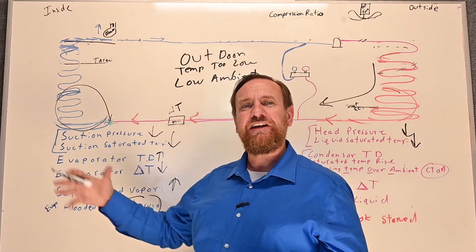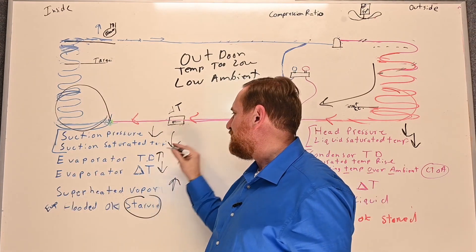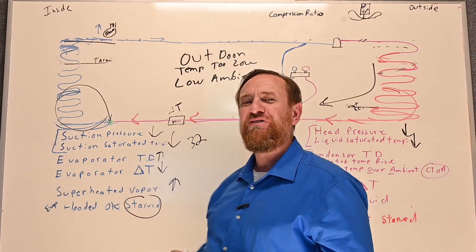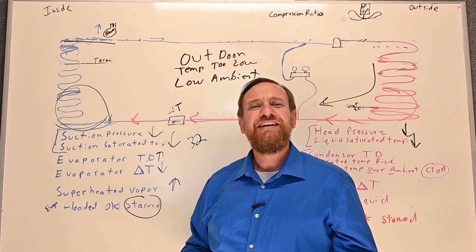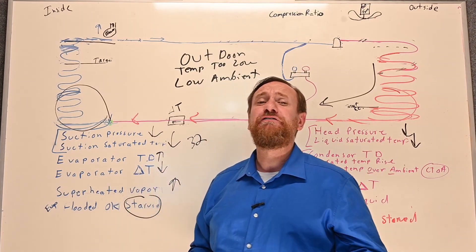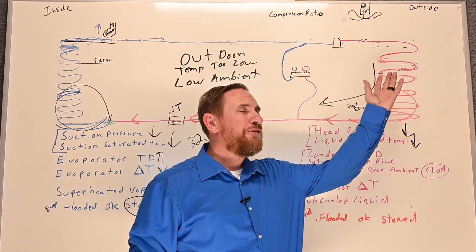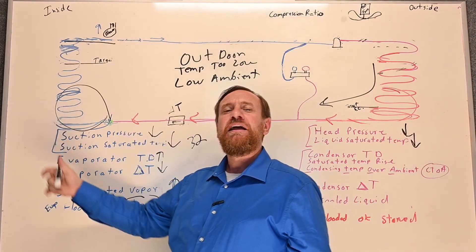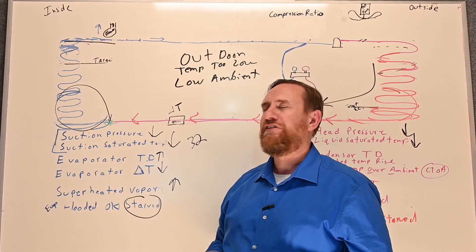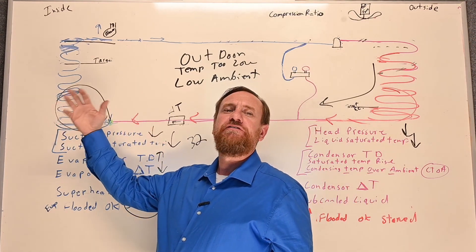So see, all that ties together. It comes together very well. Now, if that saturated temperature drops below 32 degrees Fahrenheit, what's going to happen? This system will freeze and actually will freeze very quickly. As that outdoor temperature drops and I get less pressure in this side dropping, I end up with that evaporator coil freezing. So this could be a very big issue with it freezing.